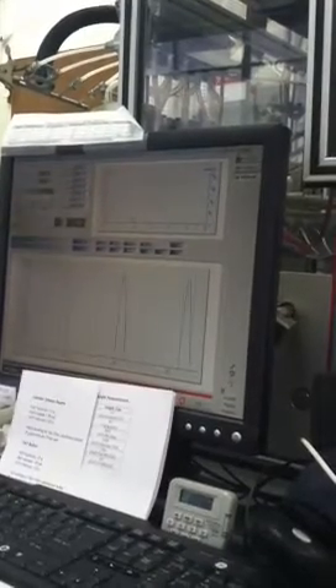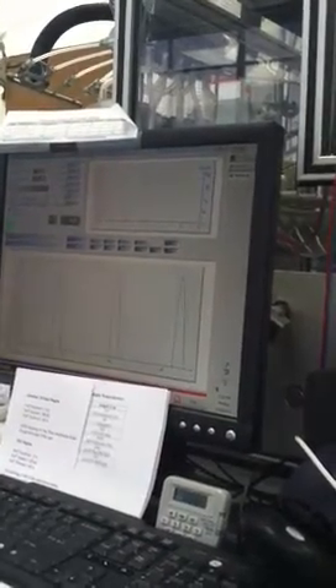Hey, that's awesome. Great. And how many times will we check it? Just 3 puffs. If, let's say it gave me 36.0 for my average volume, that would tell me that I need to rerun the volume calibration because it's obviously off. Does that make sense? It does. So, great statistics, I love it. So just hit stop cycle, you can record that number as your average volume, that's acceptable.